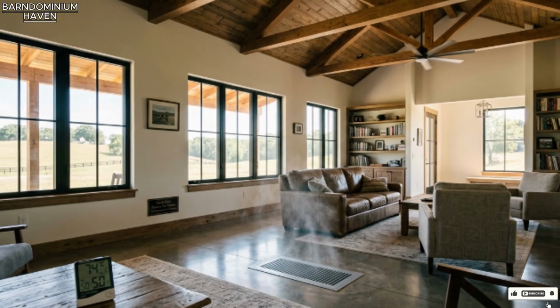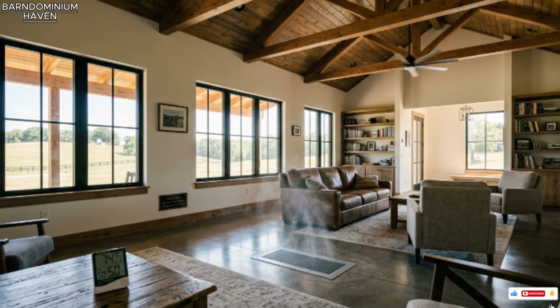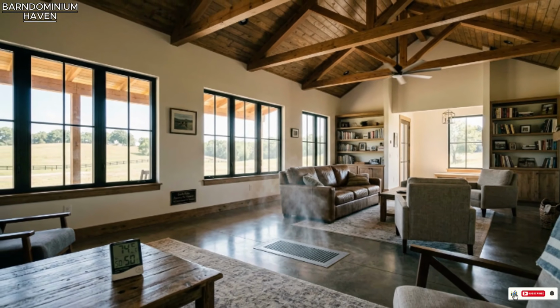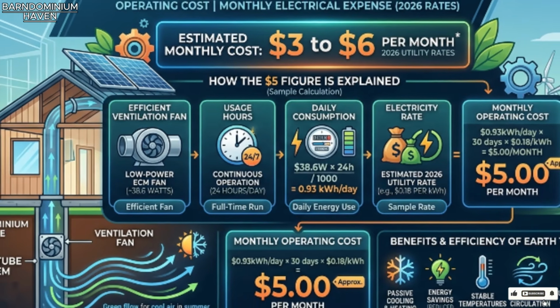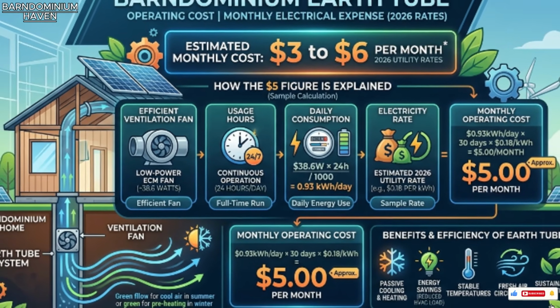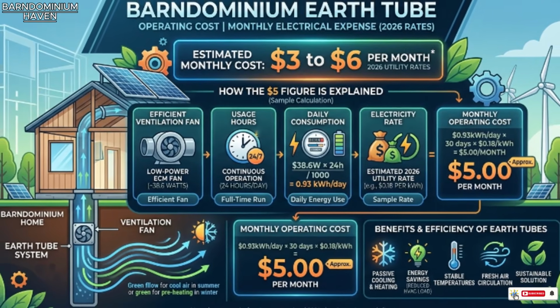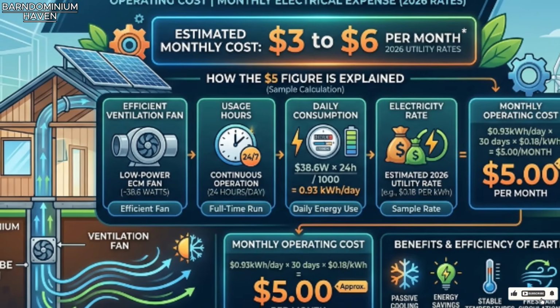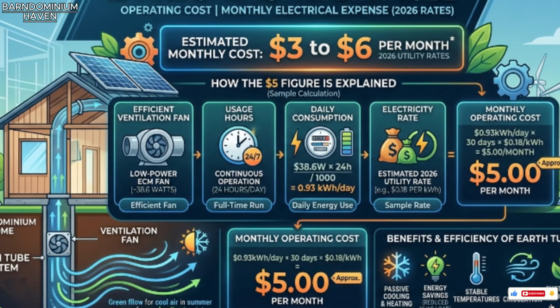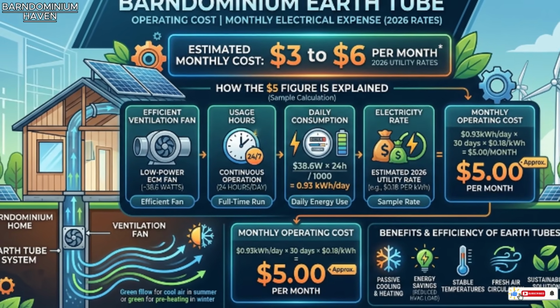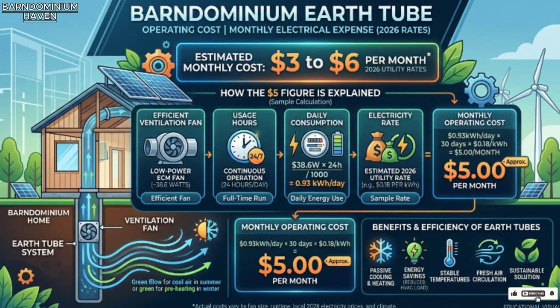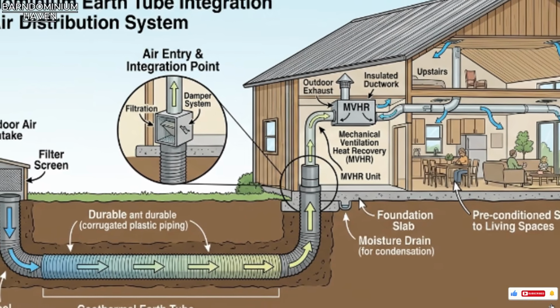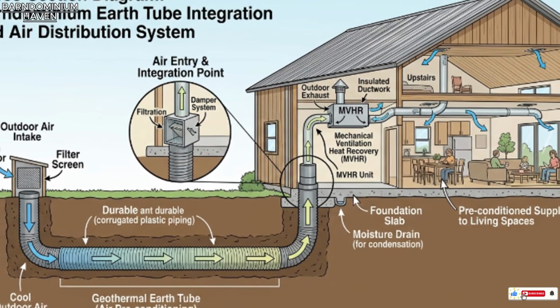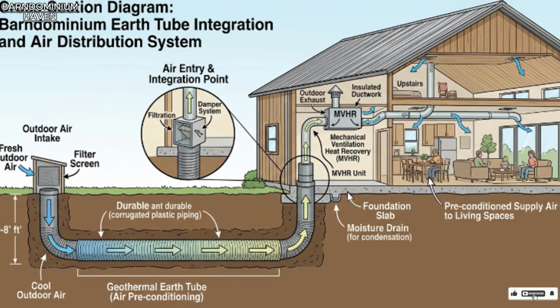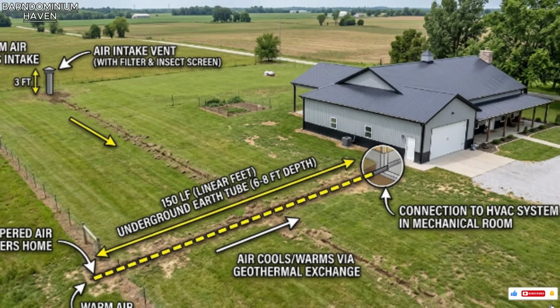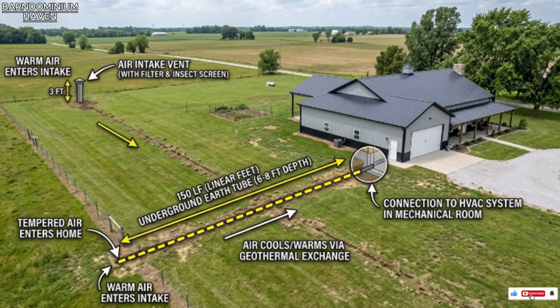Typically a small, variable speed fan consuming 15 to 40 watts, which, running continuously, costs approximately $3 to $6 per month in electricity at 2026 average utility rates. That is the $5 a month figure in this video's title. It is not marketing. It is the actual electrical cost of moving air through a pipe in the ground. The only energy input required by a system that uses the earth itself as the cooling medium.